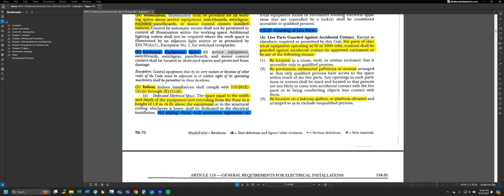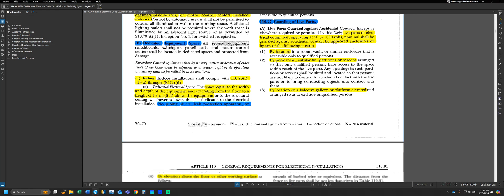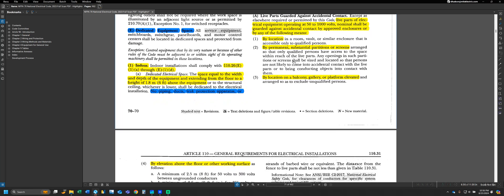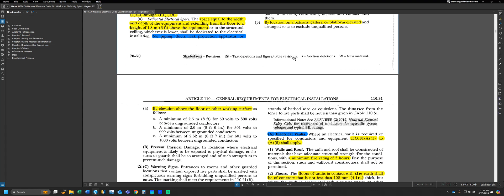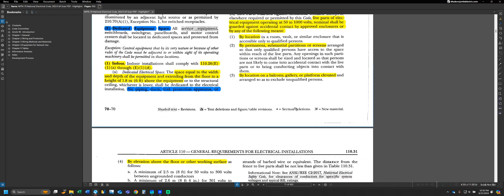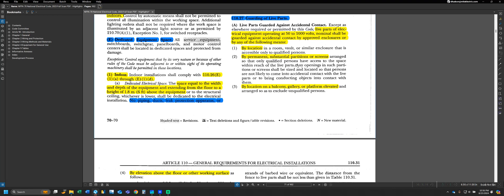In breaking down those two other options, we can see number one by location in a room vault or similar enclosure. I'm going to group that together with number three by location on a balcony, gallery, or platform elevated, and number four by elevations above the floor or other work surface. That would be our kind of location requirements. And then we can see number two here, by permanent substantial partitions or screens arranged so that only qualified persons have access to the space within reach of the live parts.